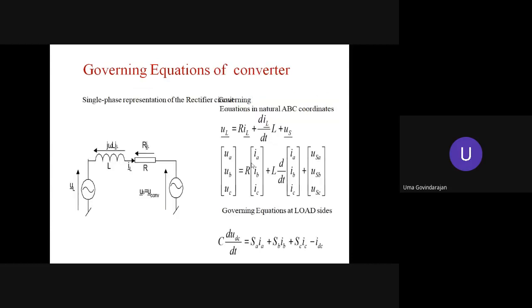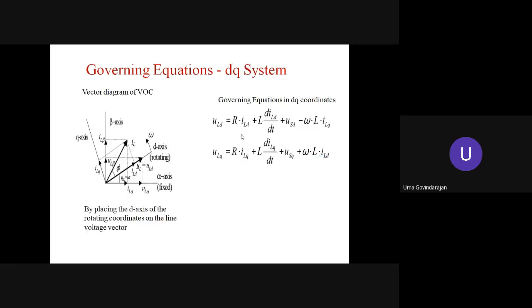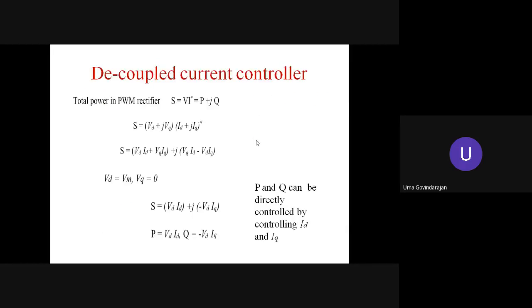Okay. So now the governing equations for the DQ coordinates, decoupling the ABC into DQ. You are converting, and I have written this expression for the DQ frame, the same ABC to DQ. We have the transformed voltages and the transformed currents in the DQ frame. Now if we employ a decoupled current controller, it is possible to have independent real and reactive power control. So the decoupled current controller is nothing but, whatever the power generated from the wind turbine, on the grid side we can go for reactive power control.